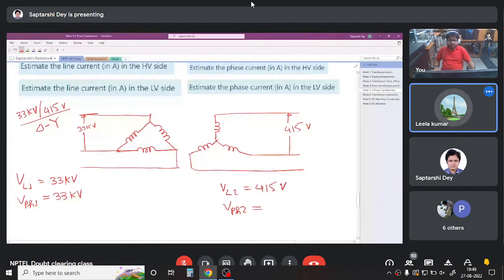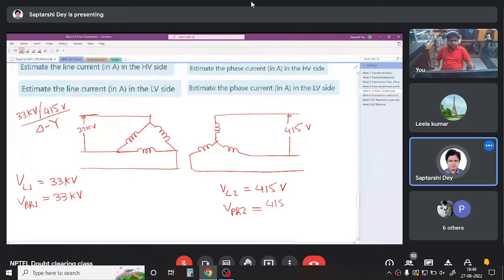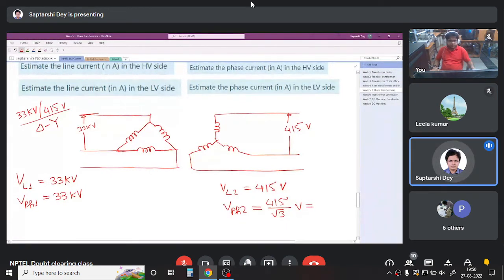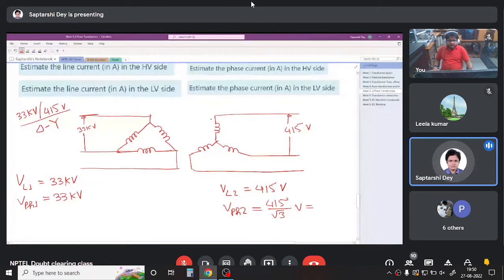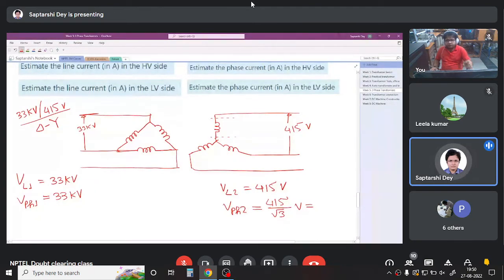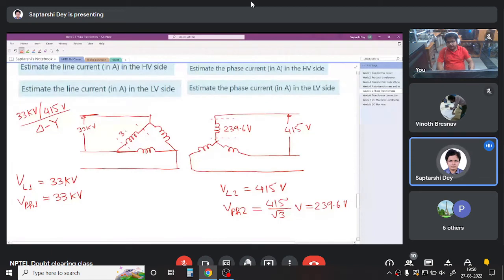Divided by root 2, no? 415. No, not by root 2, by root 3. So it will be 415 by root 3. Please, someone do it and tell me the value. So all these windings in the secondary side are not rated for 415 volt. They are rated for 415 divided by root 3 volt. How much is it? 239.6 volt. So these windings are rated for 239.6 volt, whereas these windings are rated for 33 kV.